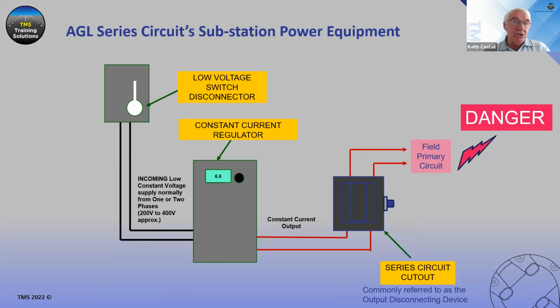In that, going back to the substation, the vault, the switch room, we want to build in, wherever possible, some protective devices. So we have a protective device for the incoming power supply to that constant current regulator. And we have a facility to be able to isolate and to earth down the field circuit on the output side of the constant current regulator. The output side is what we know is the danger, because that's where we are going to actually do some work out in the field, so the output disconnecting device is a very useful piece of equipment to have. It can be attached and part of the CCR, or it could be in a separate place in the substation.